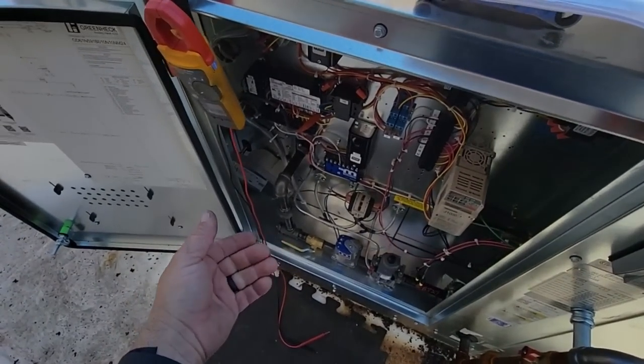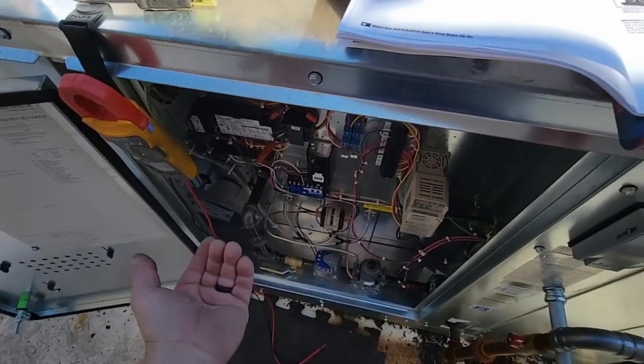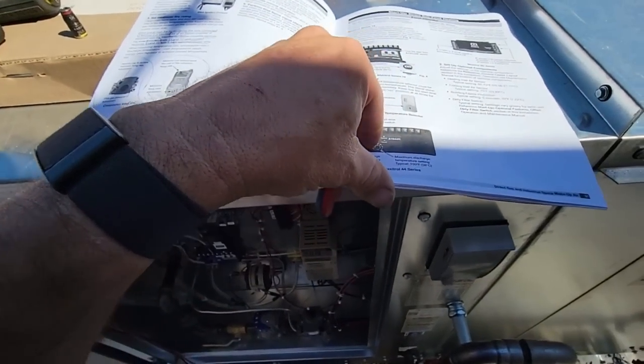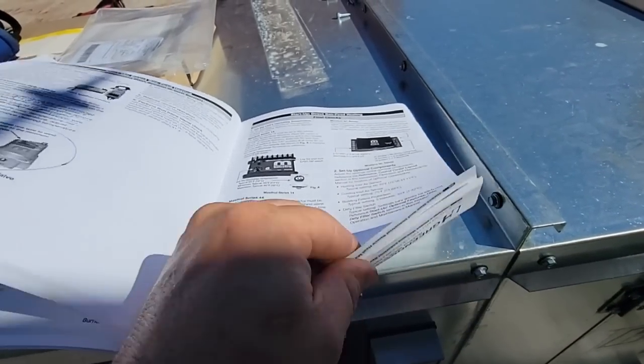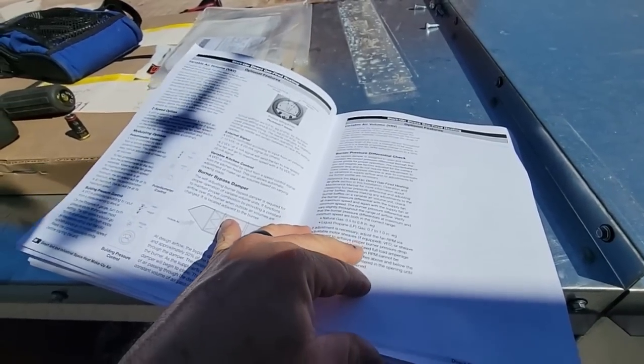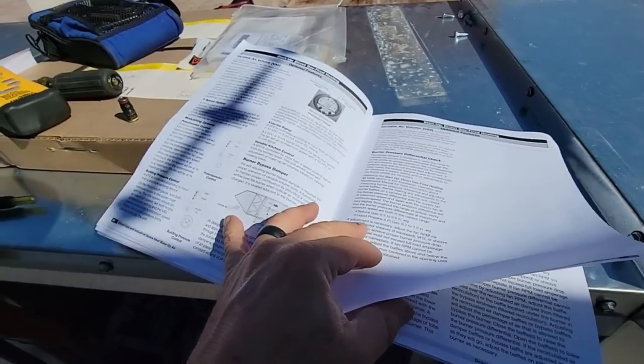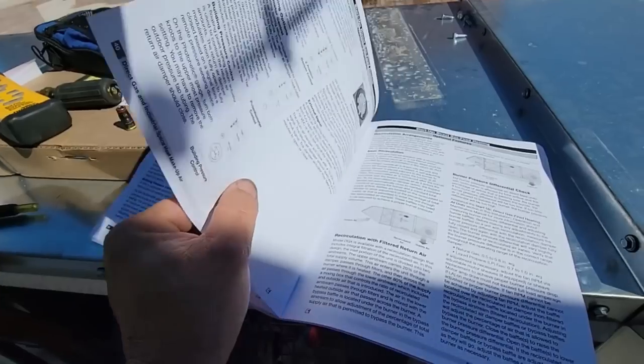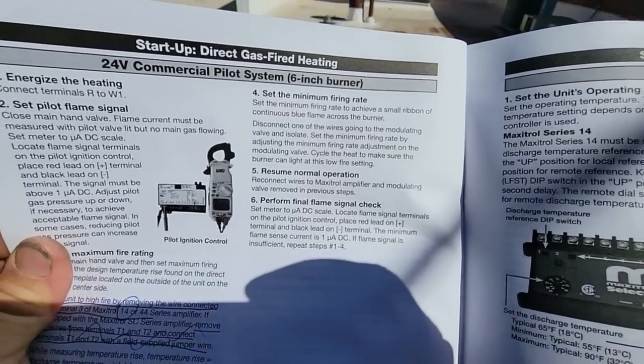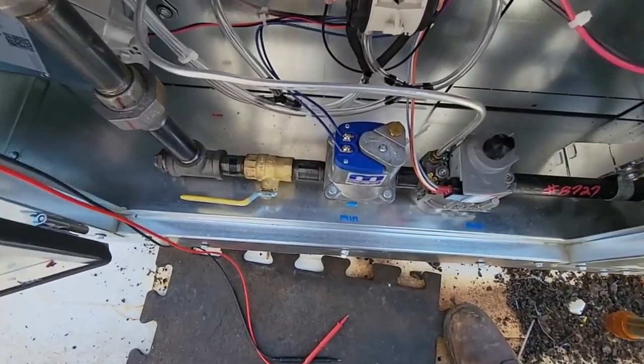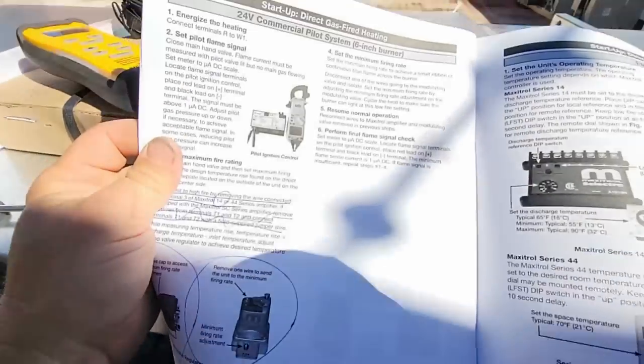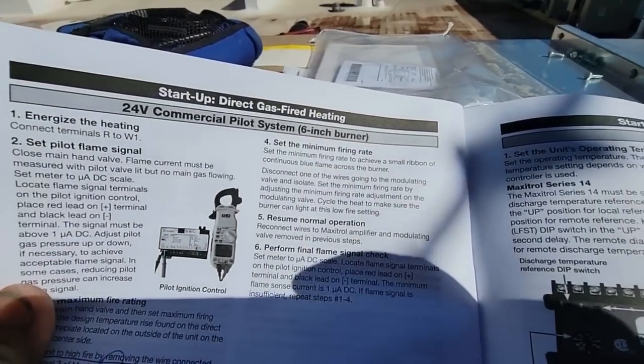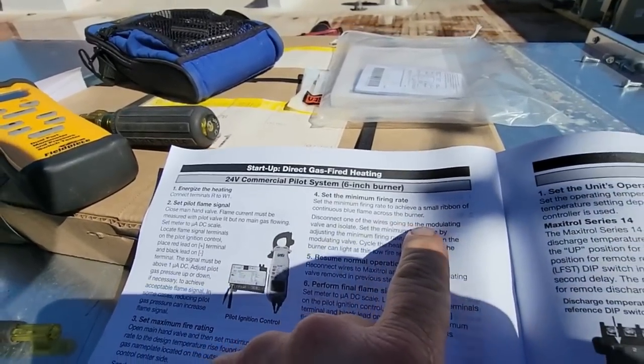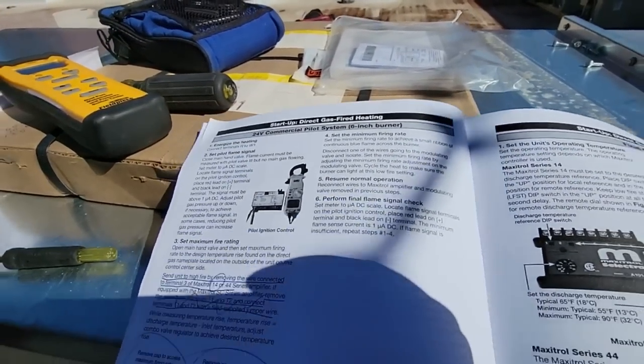The minimum is just so you don't overfire when you're in mild temperatures like this. It just gives it a heck of a back and forth with the control trying to maintain that 65, and if it's too high on that minimum, that could cause a bunch of issues there. Our minimum's set by just taking one of the wires off the modulating valve there and having it call for heat, and just have yourself a small ribbon right across the burner. So that's about all you got to do on that.